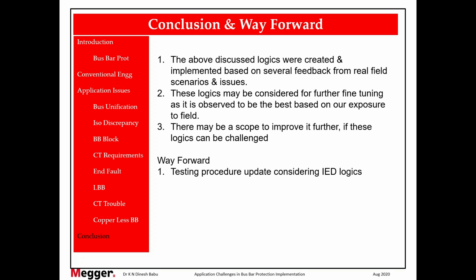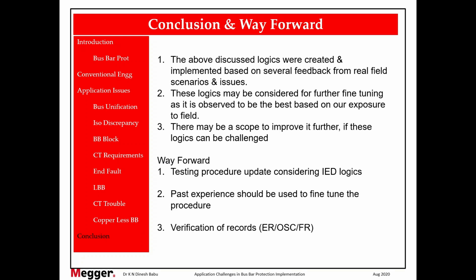All this information, all these solutions, are already available in the numerical relay. But unless we test it, we don't know whether it is enabled or disabled. That is the status of IEDs. Past experience and previous fault analysis should be considered while preparing this testing procedure. And every time a fault occurs, we have to verify the ER, OSC and FR. The oscillograph file, OSC, is currently available in all relays. So we should be able to play back that file in the new system which we are implementing, to ensure that the new system does not have any kind of glitches which we have faced earlier.